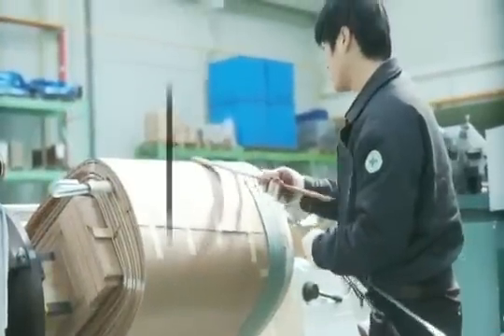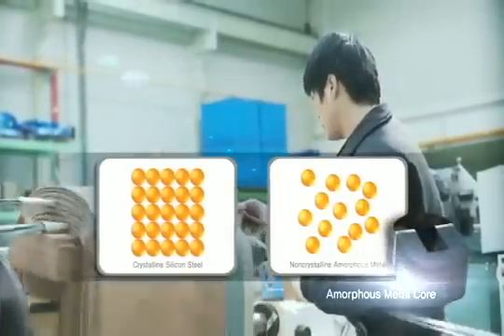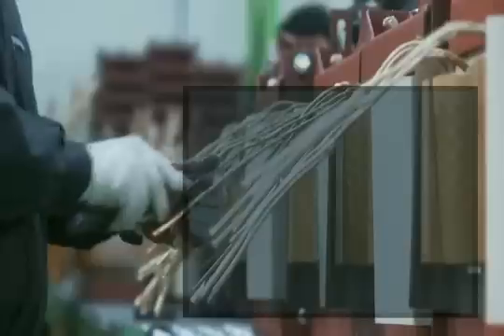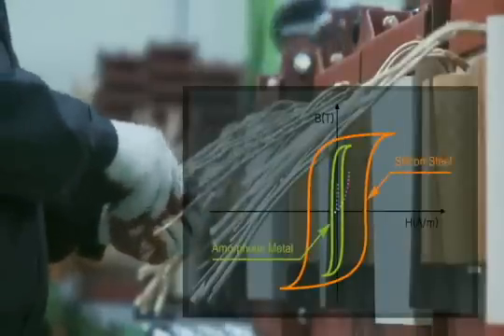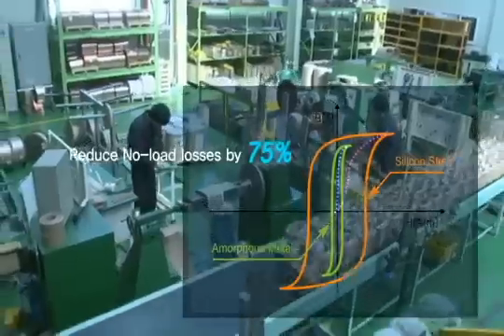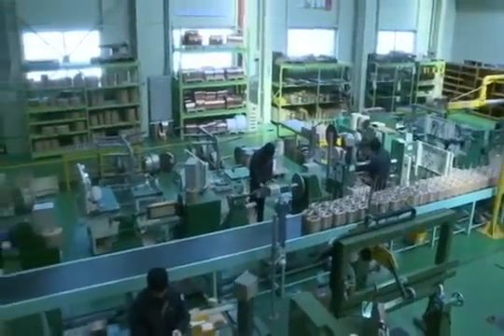The key to the amorphous transformer technology is that the magnetic core uses non-crystalline amorphous metal, which radically minimizes the no-load losses of transformers. Amorphous transformers reduce no-load losses — waste energy for utility companies — by more than 75% compared to the conventional silicon steel transformer. These losses are generated from the magnetic core.